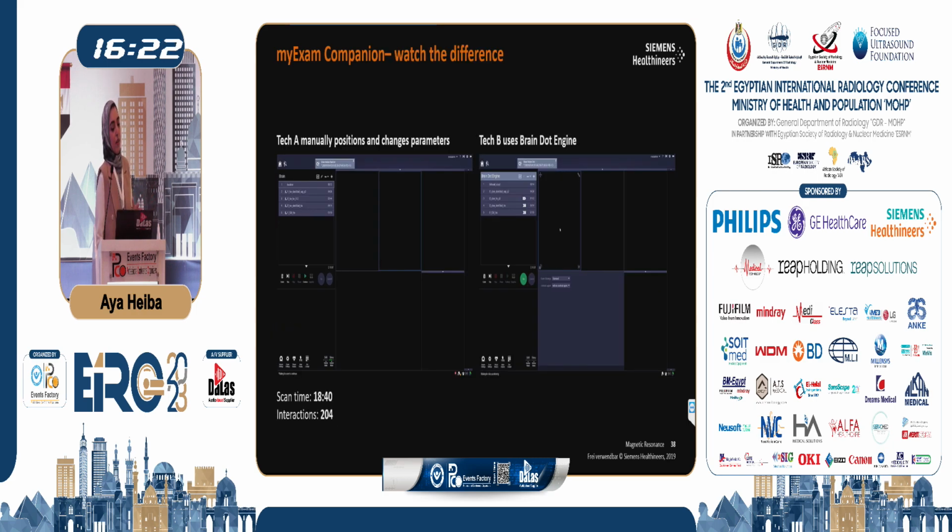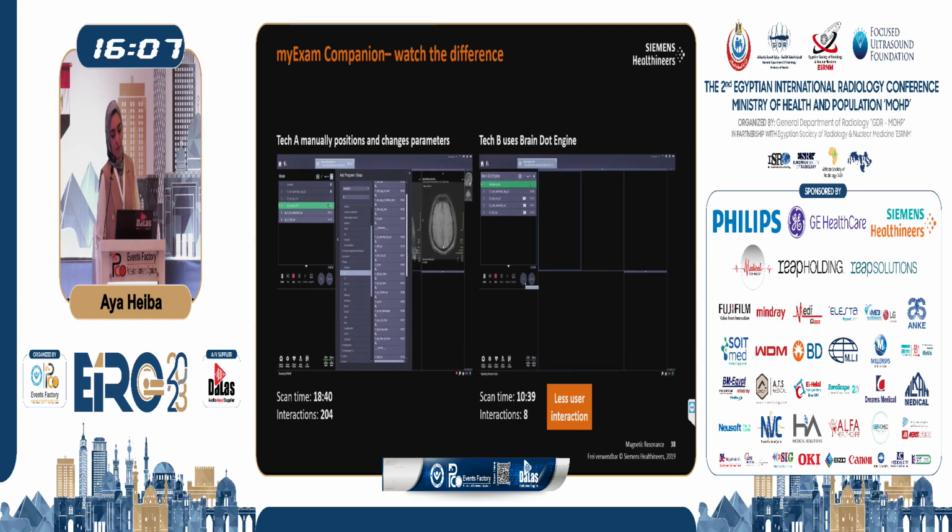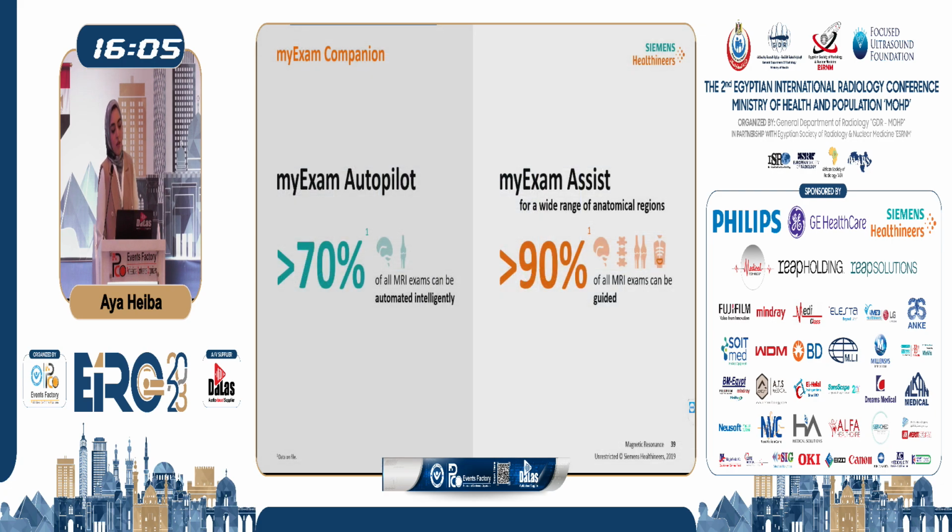If we compare an exam without My Exam Companion and with My Exam Companion, you will find that with My Exam Companion, the scan time will be only 10 minutes, but without it, it will be 18 minutes. My Exam Autopilot has guided more than 70% of the cases of MRI exams, and My Exam Assist more than 90% of the cases.